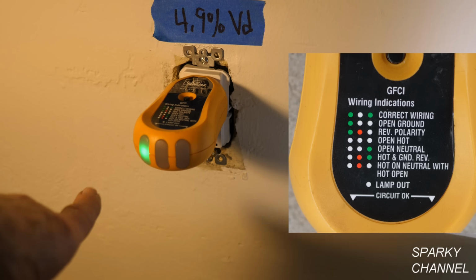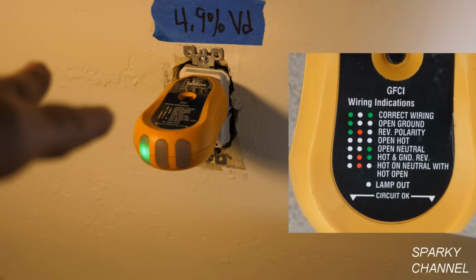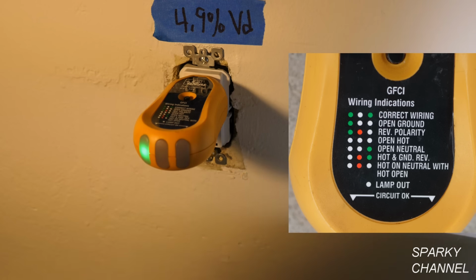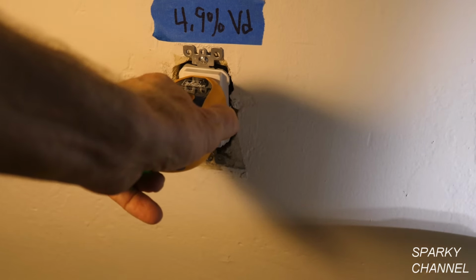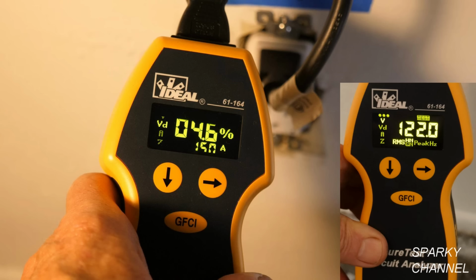Okay, I've got the circuit breaker on now, and here we have one green light. That means open ground. You have to expect that because there's no ground. I mean, this is a proper receptacle because it's GFCI, it's per code and everything. But you just get one green light. That's what you get. So I'm going to take that out. Now I'll plug in my SureTest circuit analyzer and I'll get 2 new readings for each of the new receptacles.